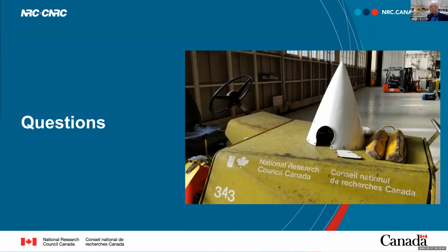Were any potential methods of battery fire suppression looked into, or was the potential of thermal runaway too high to make containment the only viable option? It wasn't considered seriously because it's very difficult, if not impossible, to stop thermal runaway once it's begun. Everything required for sustainment of that fire is present, and as the battery burns it actually produces its own oxygen to sustain the fire. So suppression was not seriously considered. We elected to contain and prevent propagation to the rest of the modules.